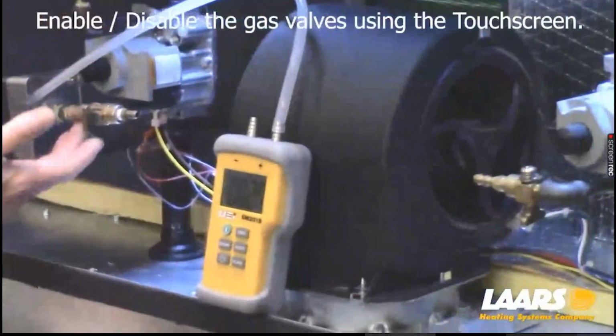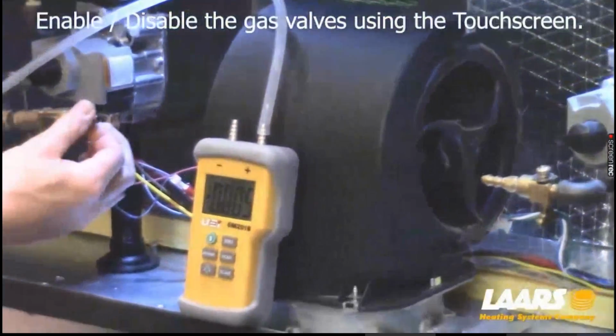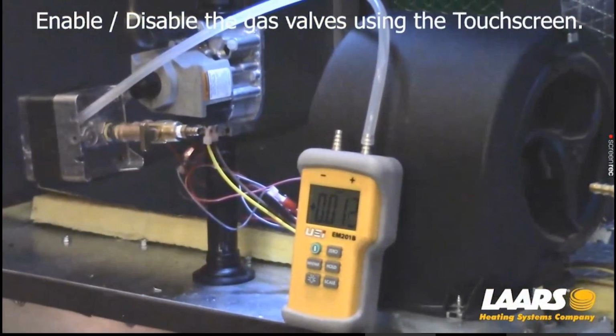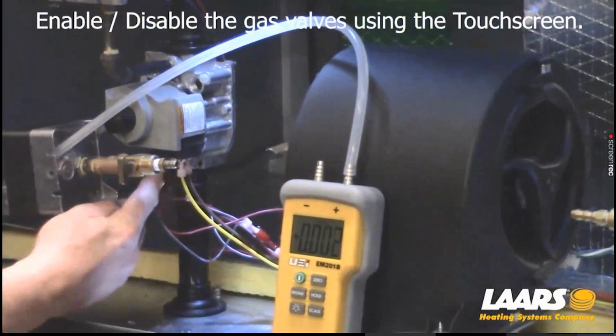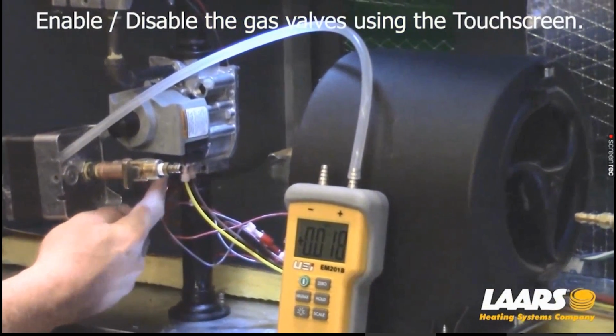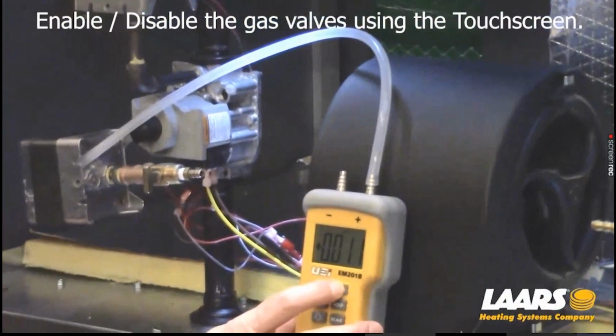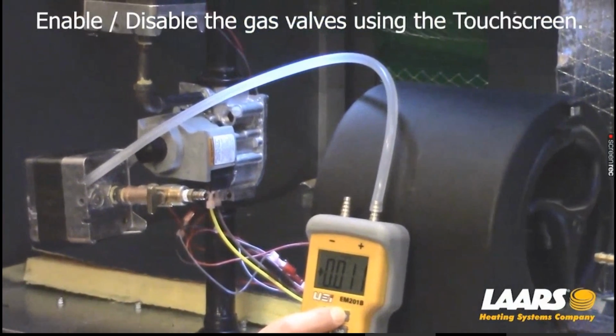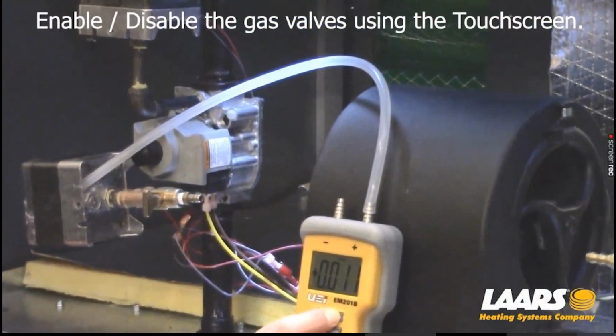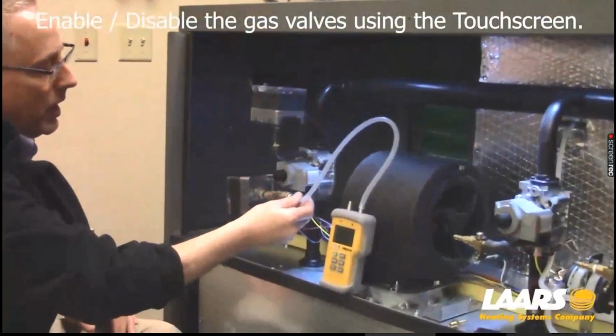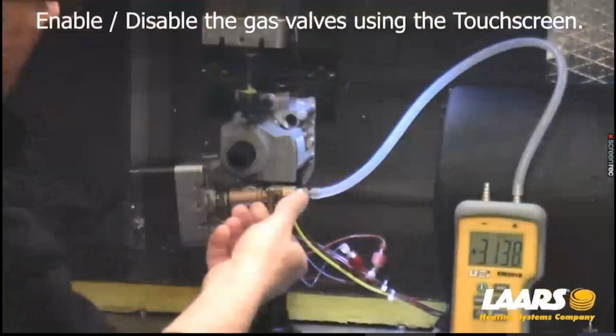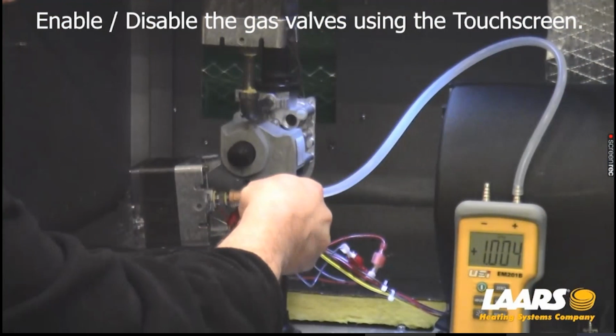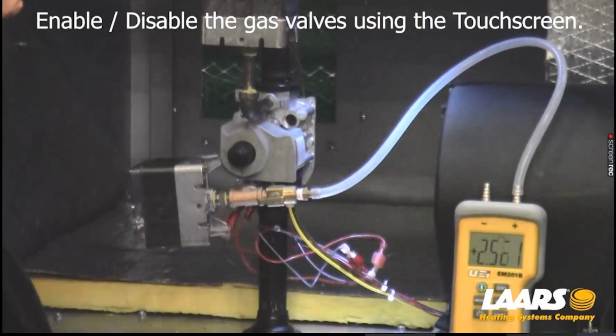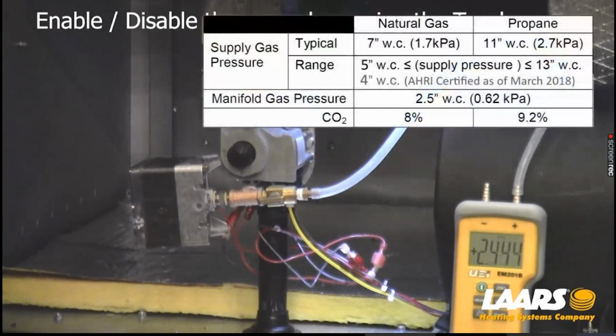If I have CSD1, I'll have this butterfly valve set up. I've already put this barb in for my manometer. If not, you're going to remove the test plug on the bottom side of the valve and install your barb. Make sure your manometer is zeroed out. Now you can install the barb. I'll open the butterfly, and I'm looking for 2.5 inches of water column. As you can see, I'm running about 2.4 to 2.5, which is good.